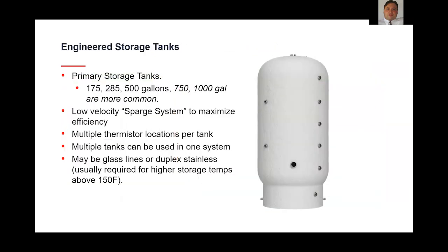So with these systems, again, because they're series tank arrangements and because of very low recharge flow rates and wanting to maximize stratification in the tanks and temperature sensing requirements for triggering on these heat pumps, these are typically not off-the-shelf tanks. Again, this may vary by manufacturer. These are usually custom engineered tanks that aren't available through normal supply channels. And so manufacturers typically will partner with specific tank manufacturers to construct these tanks specifically for their offering.